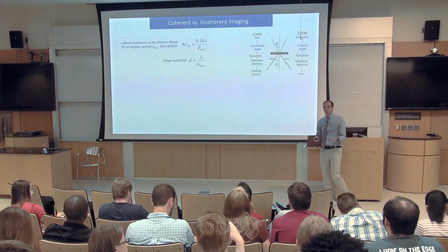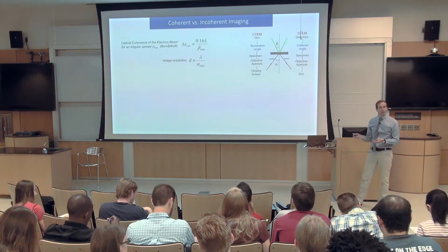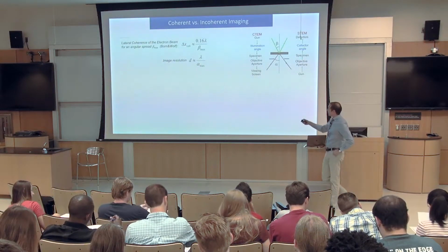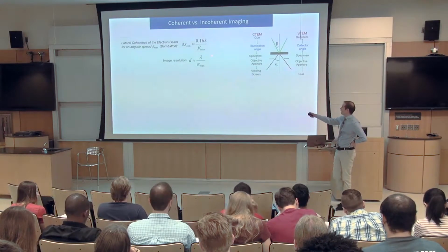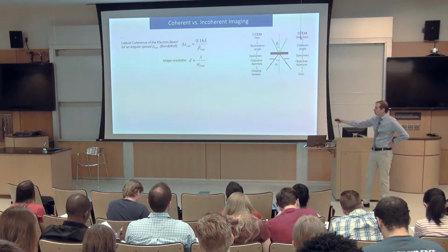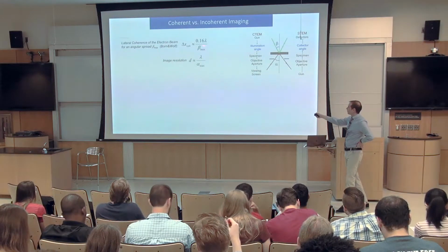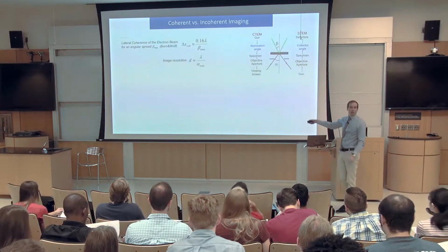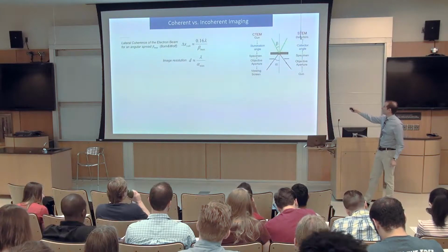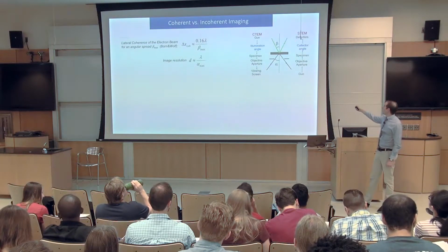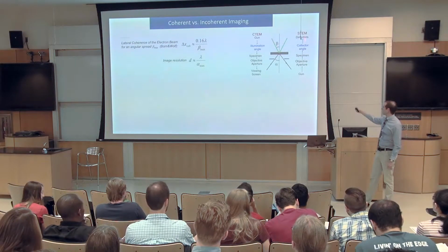That was an imaging mode for coherent imaging, like in TEM. We can also have an incoherent imaging mode. To have a coherent imaging condition, we need to consider the angular spread beta of our microscope, and it defines a coherence length. If our coherence length is large relative to our image resolution, we'll have coherence. So in TEM, the illumination angle is going to determine your coherence, and your collector angle in STEM is going to determine your coherence. This again is the principle of reciprocity.